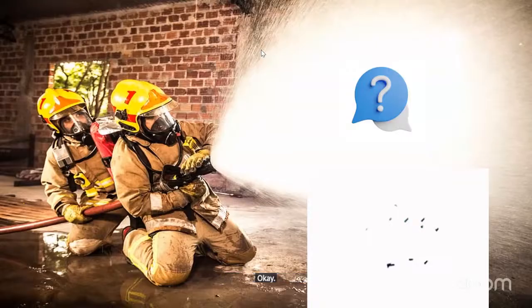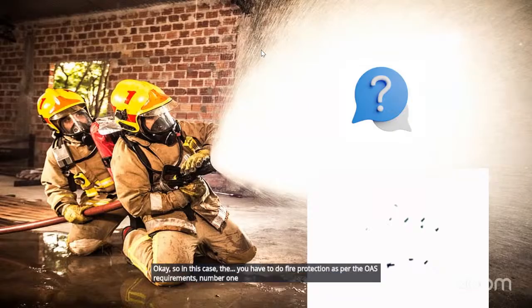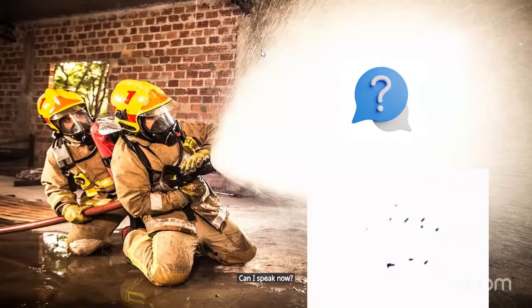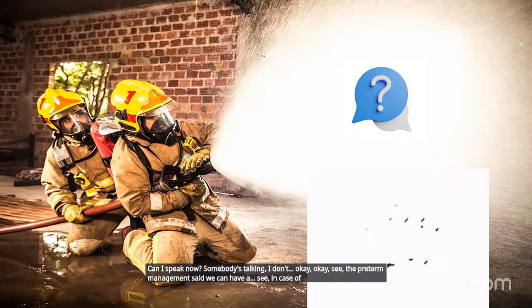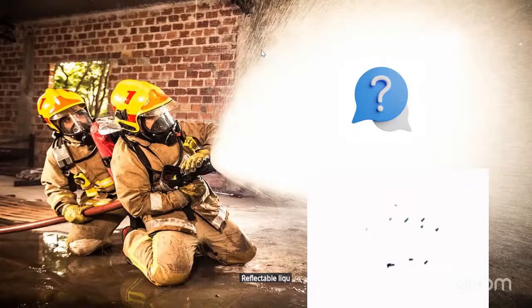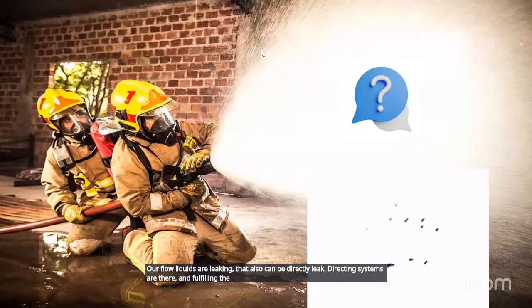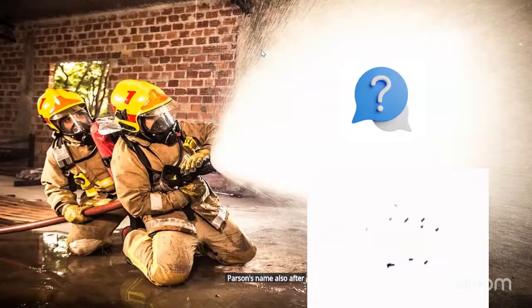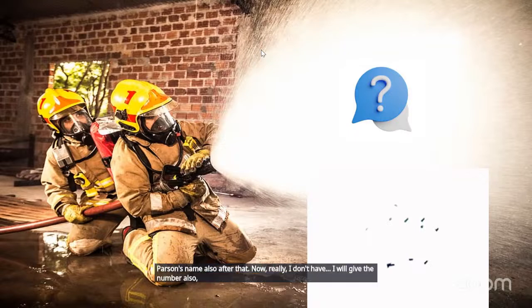Okay. So in this case, we have to do fire protection as per the OISD requirements, number 1. For predictive management, we can have a leak detector system, which is available nowadays. Gas leak detection, like an LPG leak detector, is there. Any leaking liquid or flammable liquid can also be detected. Leak detection systems are there, and preventive systems for filling up to the brim level are there. We have to employ them. I can give the person's name also later; readily I don't have it now. I will give the number also for contacting persons like this.